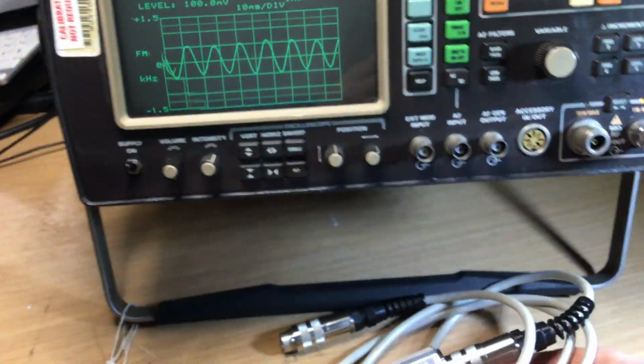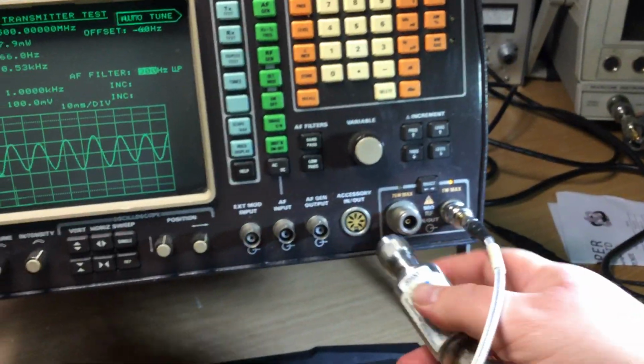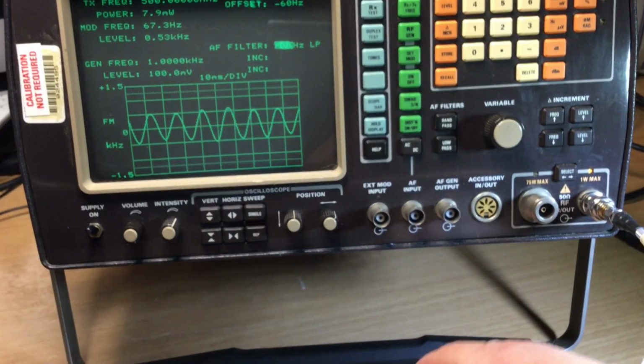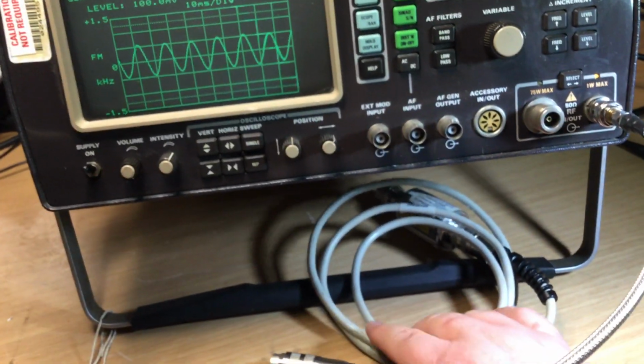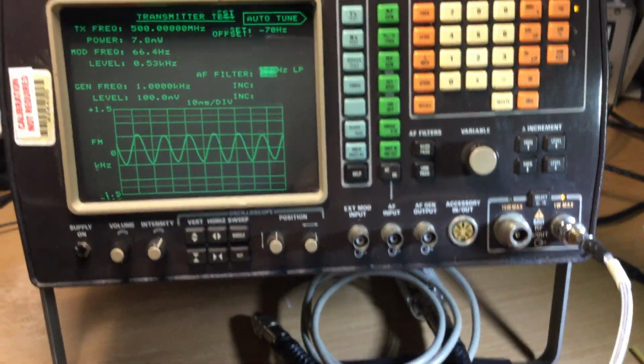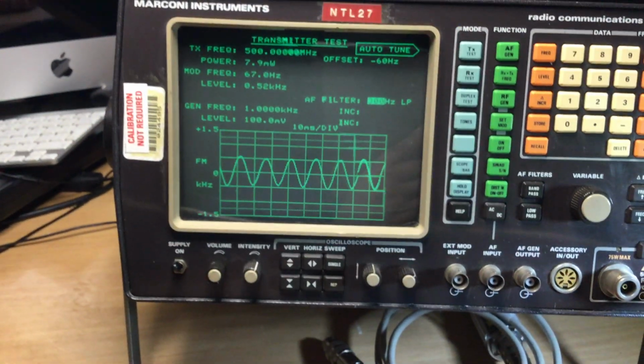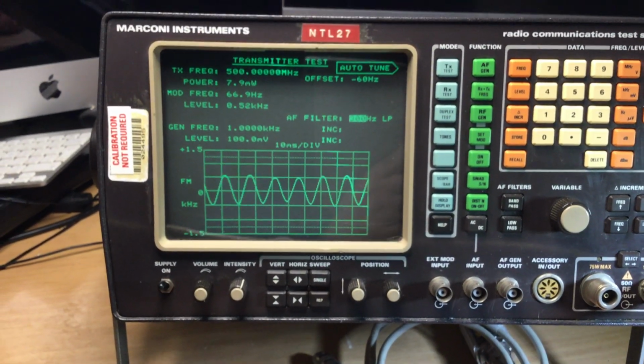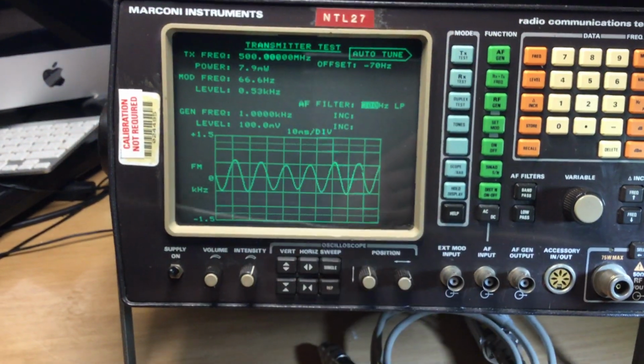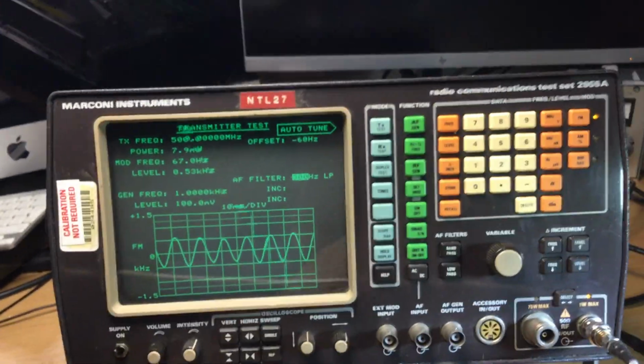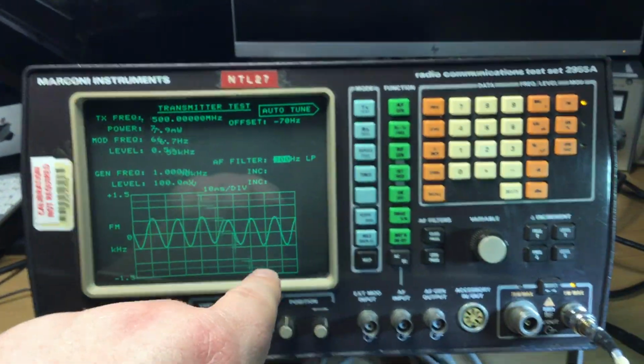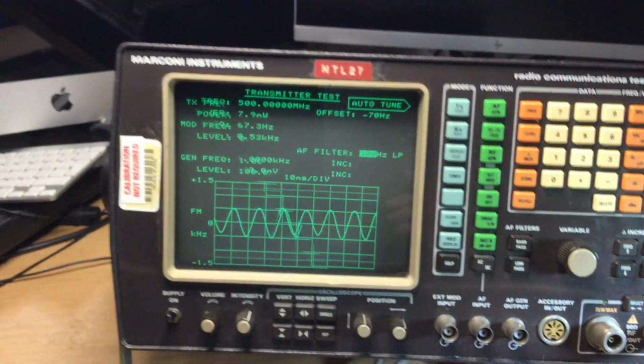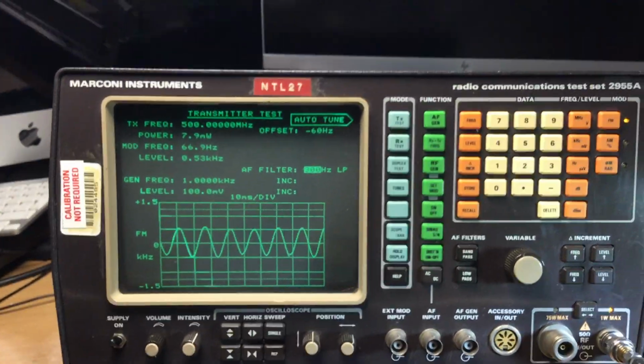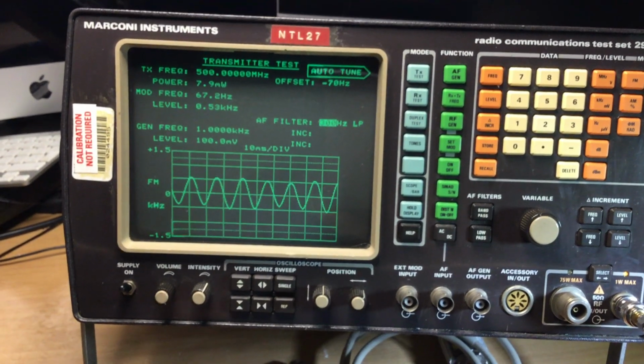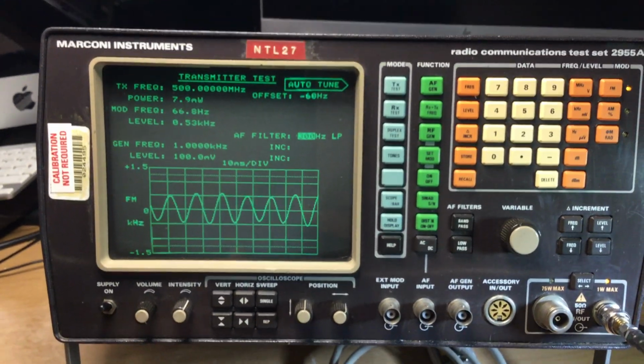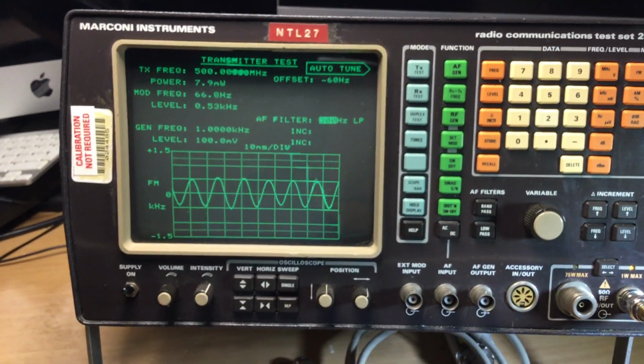is an RF power sensor, very sensitive indeed, and we would connect that on the front of here, and then to what is a power meter, because these read microwatts or very low level. So we can check the RF signal generator level right down to its lowest level, and likewise all the range right the way up to its highest level, and then we can, if need be, calibrate the instrument with the software settings to adjust the RF output level on there if it's out by a few dBs here or there. If it's massively out, like 10-20 dBs or whatever, then there's likely to be a physical fault that's causing that, not necessarily a calibration issue.